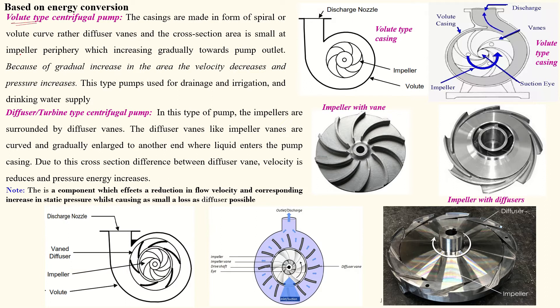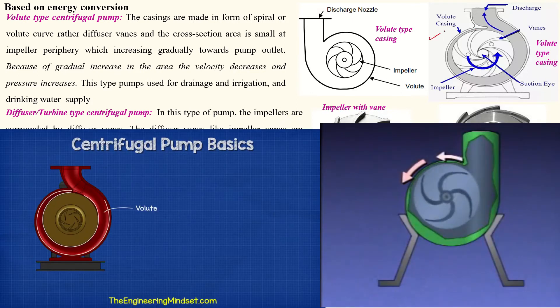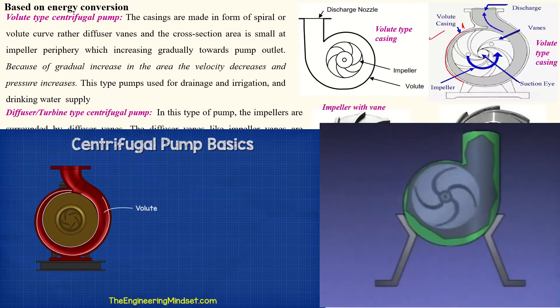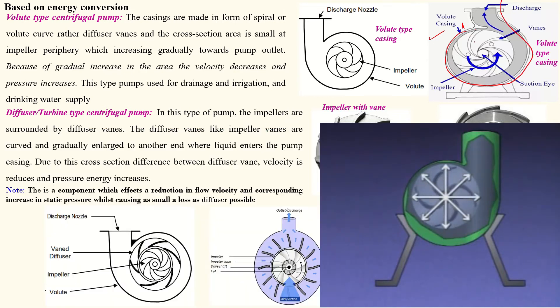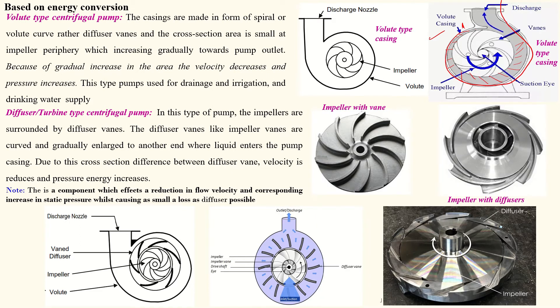The first classification is based on energy conversion. There are two types: volute type and diffuser type. In the volute type, looking at the cross-section of the casing from the top, the cross-sectional area gradually increases toward the outlet. As the area increases, the pressure head increases. This type of pump is mainly used for drainage, irrigation, and drinking water supply.